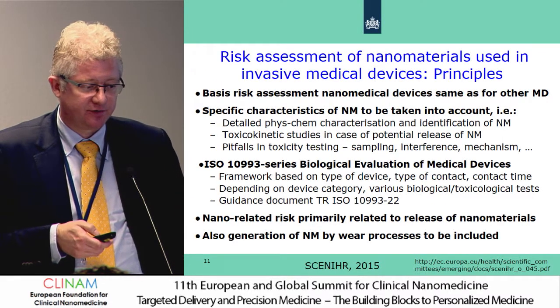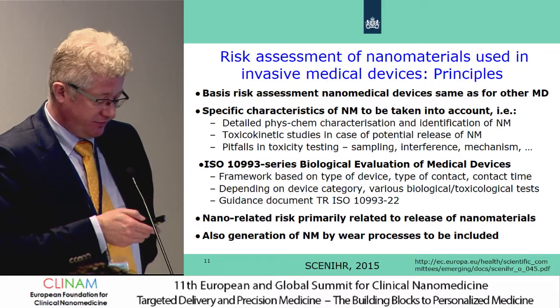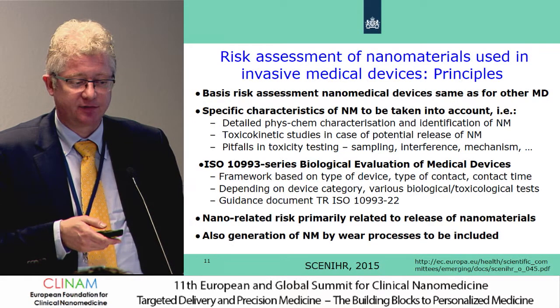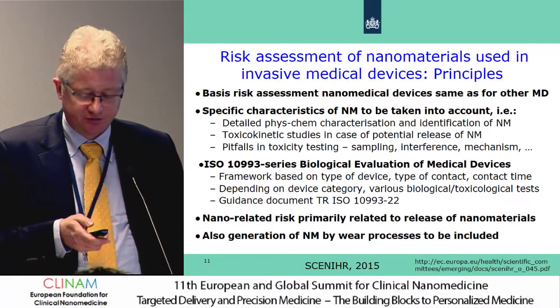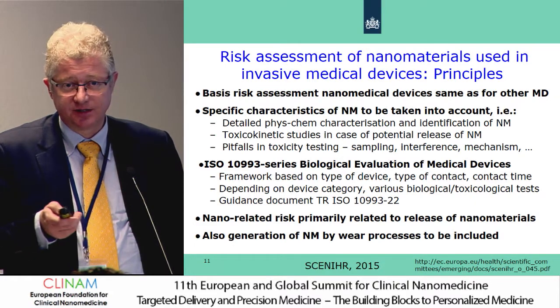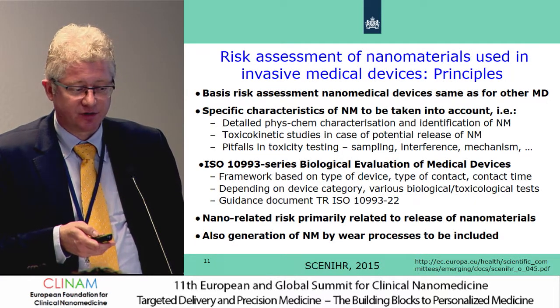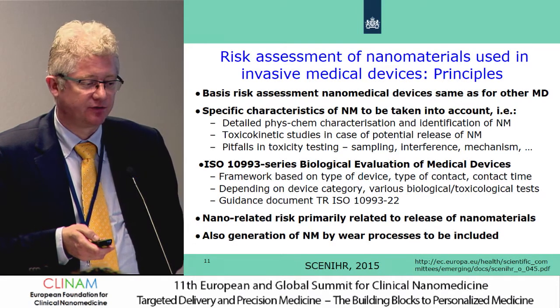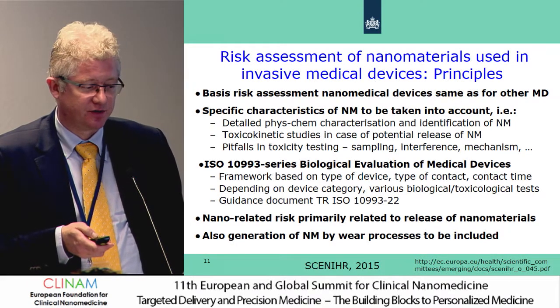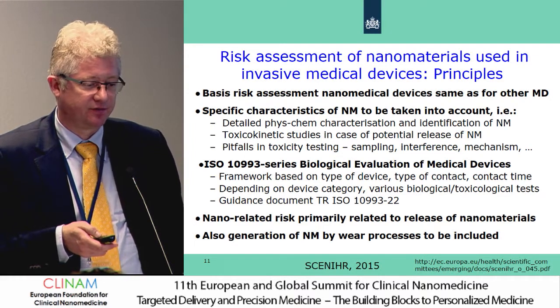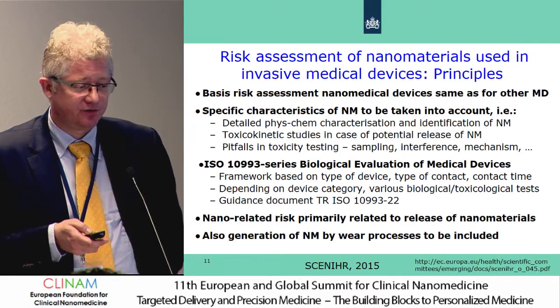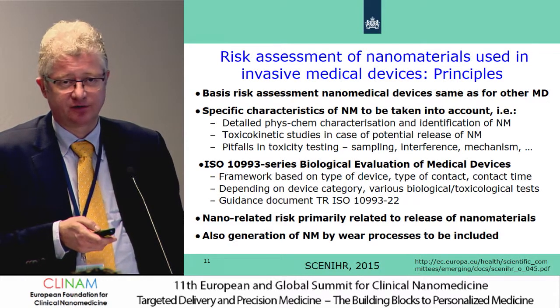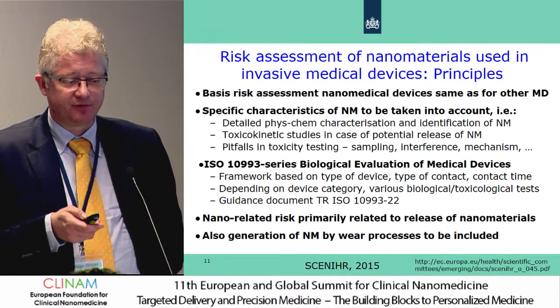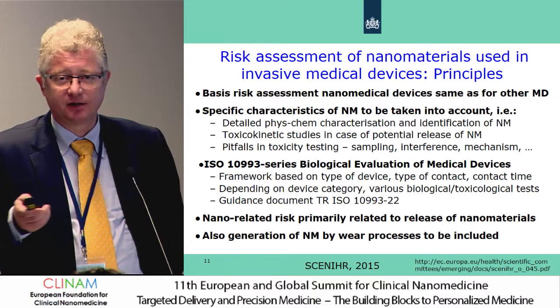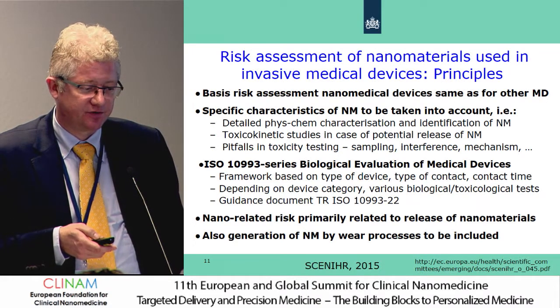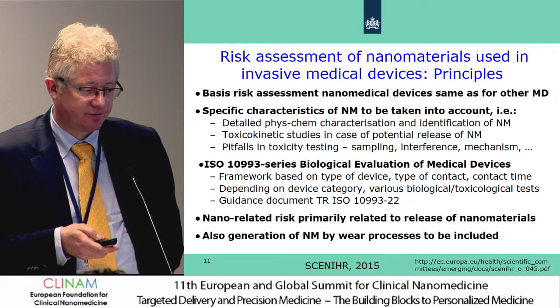If you look at risk assessment of nanomaterials in devices, what are the principles? First of all, the basis is the same as for any other medical device, and specific characteristics of nanomaterials to be taken into account are the detailed physical-chemical characterization, the toxicokinetic studies in case there is potential release of nanomaterials, and you should be aware of any pitfalls in toxicity testing, for example, the sampling, interference, and mechanisms. The standard series for biological evaluation of medical devices is a framework, and it's based on the type of device, type of contact, the contact time, and depending on these, various biological types of testing endpoints are given up for consideration.